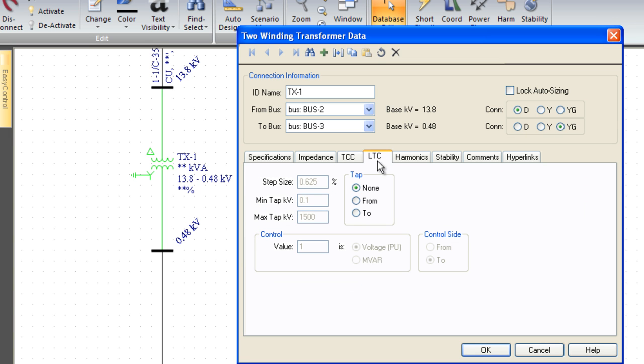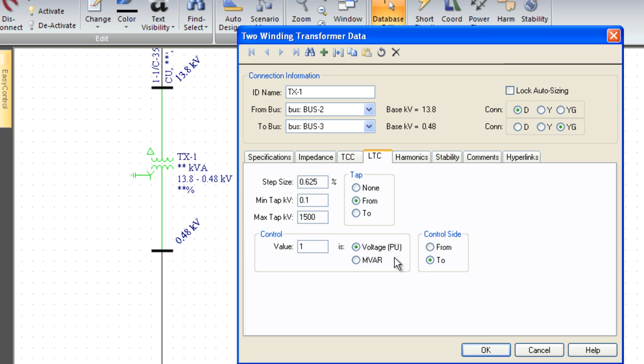We already have all the defaults necessary for the transformer damage curve such as 100% withstand, plotting unbalanced, derating, whether or not we use frequent or infrequent fault curves, the magnetizing inrush and those types of things. Load tap changers—this just allows us if we're doing a power flow study, if we want to model the from or the to side with an LTC. Controlling the from or the to side, we can control voltage or megavar flow through the transformer, any step size, any tap range.